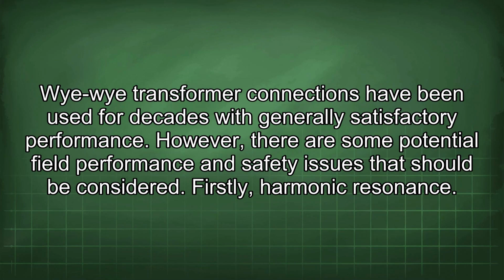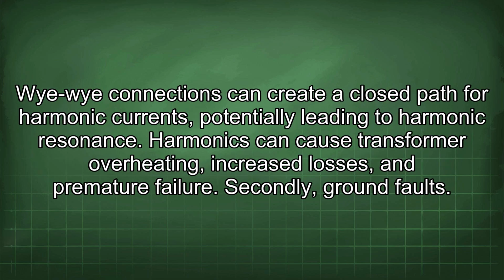Wye-Wye transformer connections have been used for decades with generally satisfactory performance. However, there are some potential field performance and safety issues that should be considered. Firstly, harmonic resonance. Wye-Wye connections can create a closed path for harmonic currents, potentially leading to harmonic resonance. Harmonics can cause transformer overheating, increased losses, and premature failure.